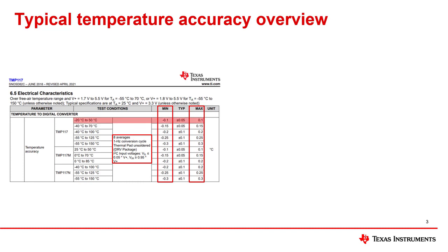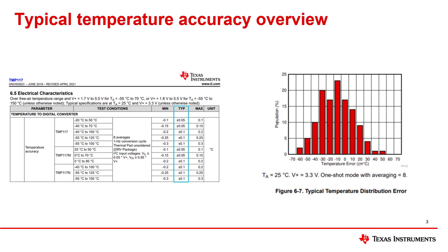For example, this first line shows the plus or minus 0.1 degrees maximum accuracy from negative 20 to 50 degrees Celsius. The typical temperature accuracy is the accuracy you would most likely encounter if you selected a random unit from a batch of temperature sensors and used it to start taking measurements. It is not the worst case temperature error like the max accuracy, but rather the most commonly seen error in a normal distribution curve from a population of temperature sensors. The typical temperature accuracy will always be a smaller absolute value than the max temperature accuracy, since the max temperature accuracy will be a certain number of standard deviations away from the typical accuracy, depending on what worst case temperature error was determined to still be allowable for operation.